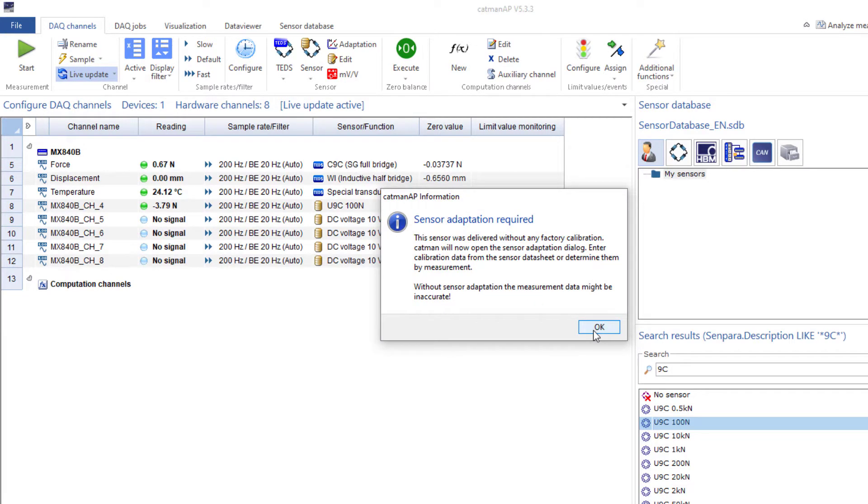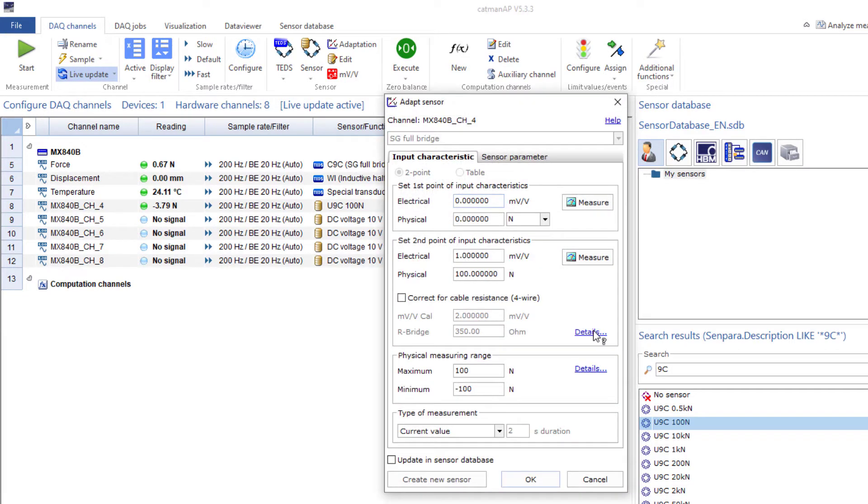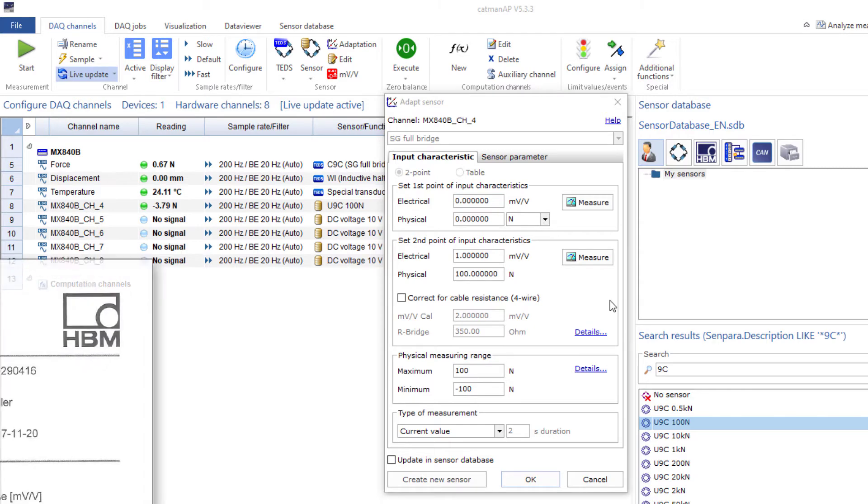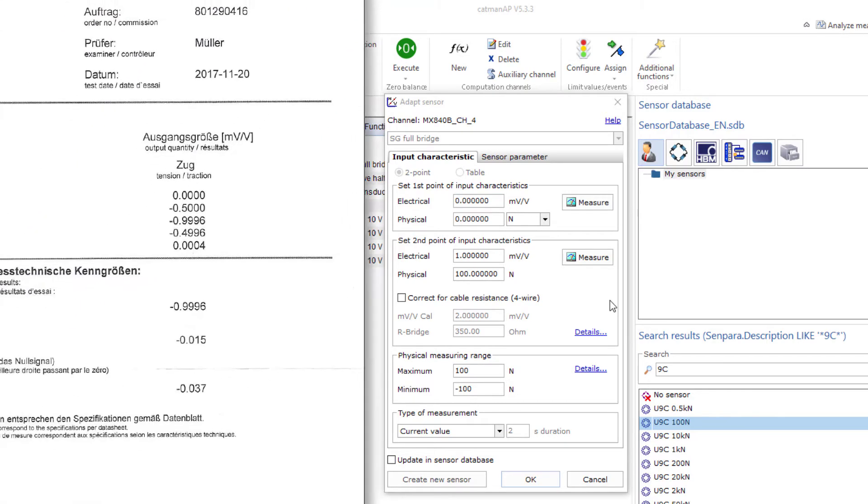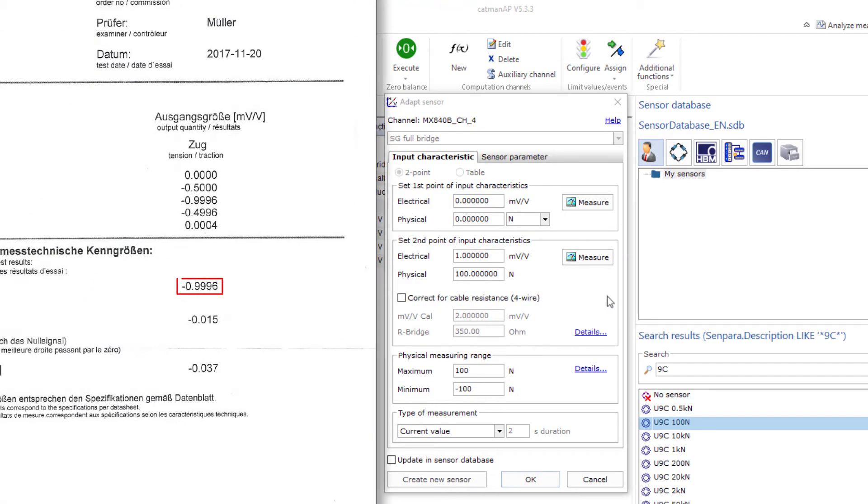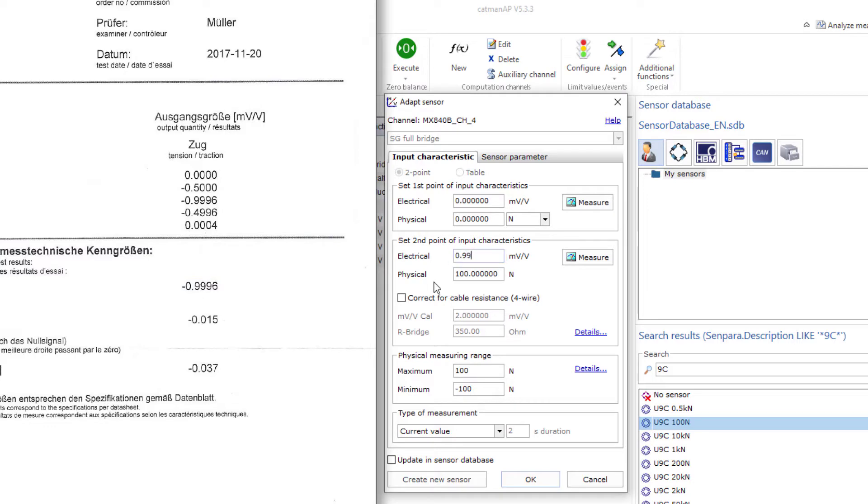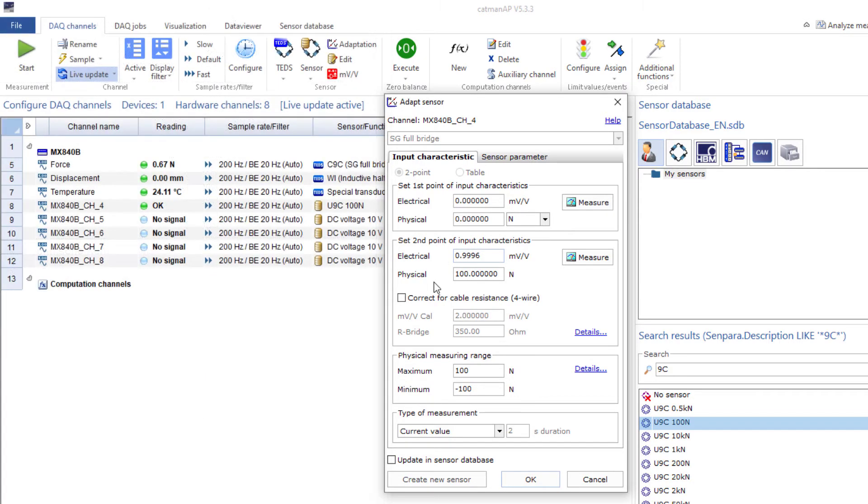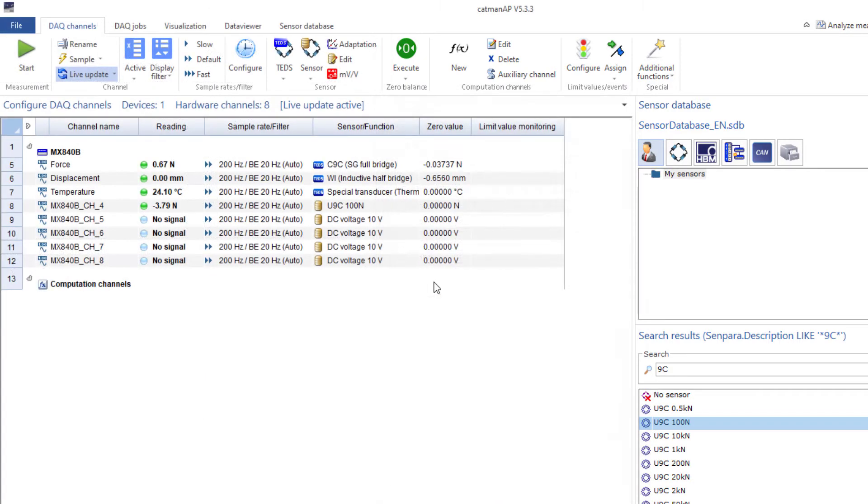Now a window with a dialog opens. Why? Because the database initially only contains the nominal values of the sensor. Of course our sensor has very specific values, which can be found in the calibration protocol. Therefore, enter your sensor's sensitivity value here. That's it.